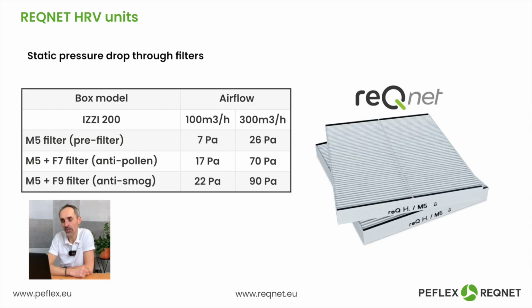As for the filters, when it comes to our RecU series devices, we can use a set of filters like the M5 and F9 types without affecting the device's performance. However, if we wanted to use such an external filter box with the IZZI ventilation unit, we have to take into account that the M5 plus F9 filter set can create resistance at the level of 90 to 100 pascals, so we also need to factor that into the calculations and selection process. When calculating installation resistance, remember that the filter box adds 100 pascals of resistance, so include that in the total resistance.